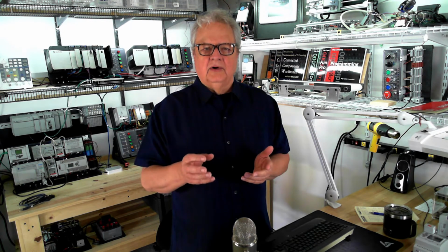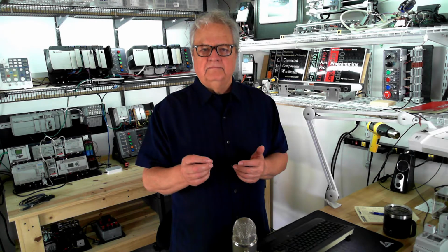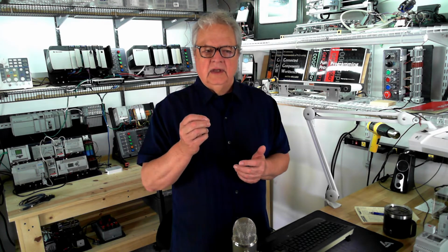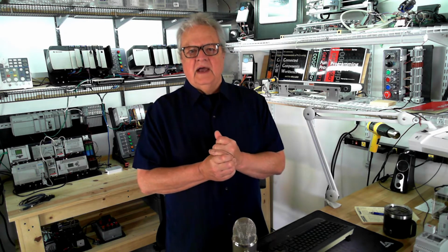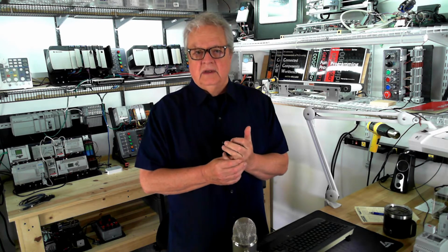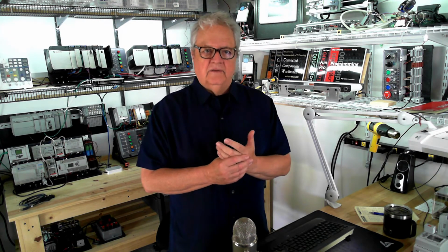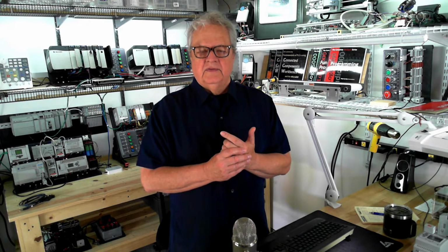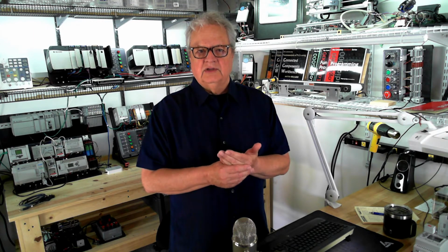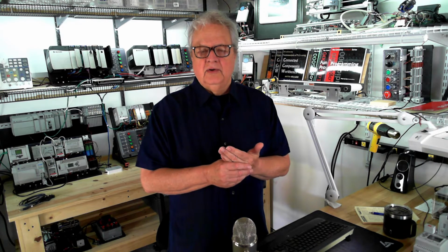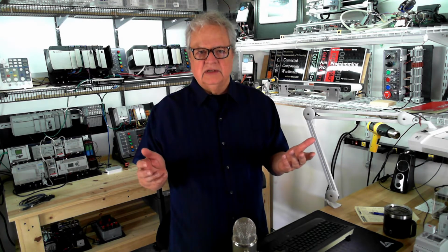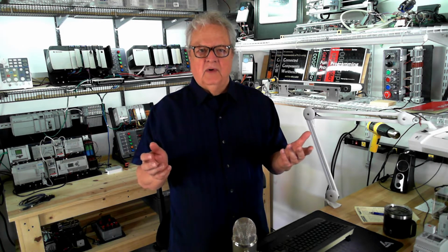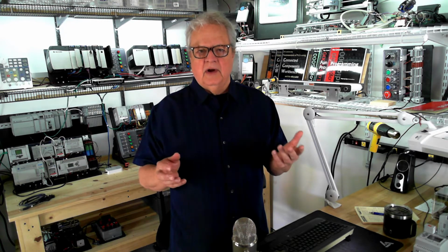So a timer is going to count units of time. Now, the newer controllers, processors, typically count in thousandths of a second, milliseconds. Some of the older stuff gave you the choice of thousandths of a second, hundredths of a second, tenths of a second, or seconds. Now with the Micro 800, you have at least thousandths of a second. Typically, I always use milliseconds because that gives me more resolution if I want to adjust the time and I want to make it really tight.